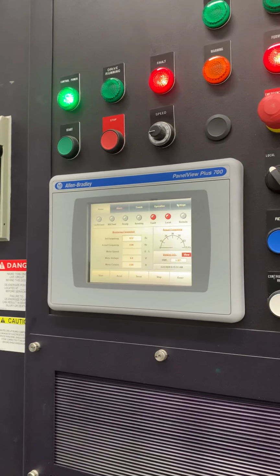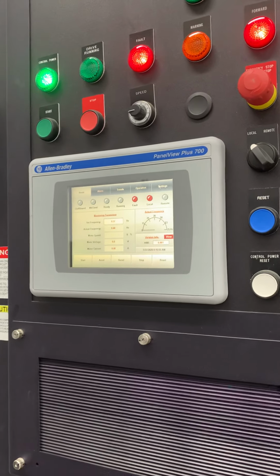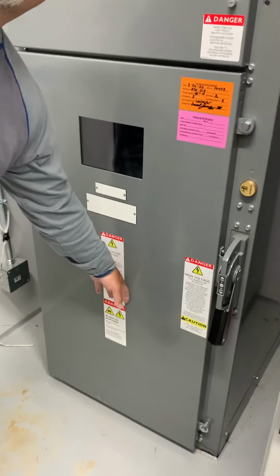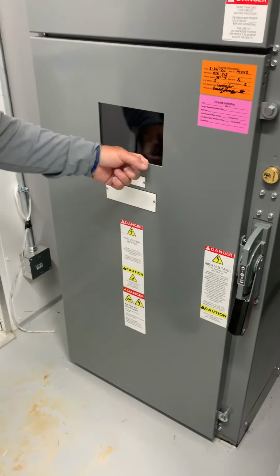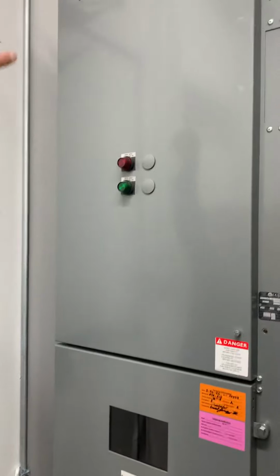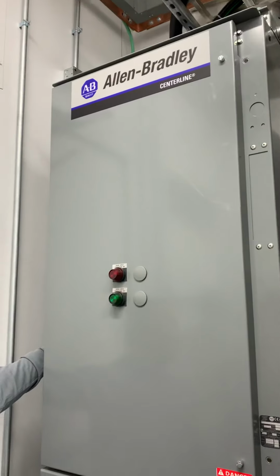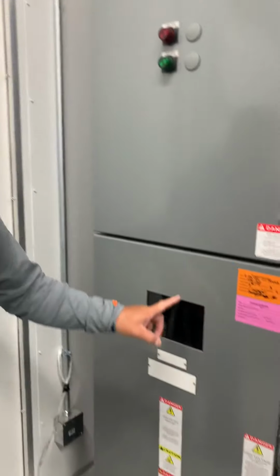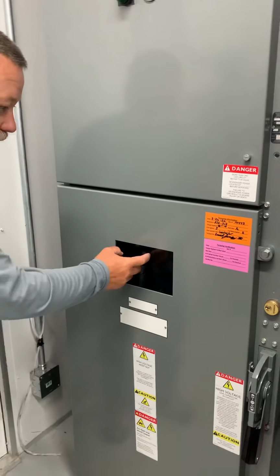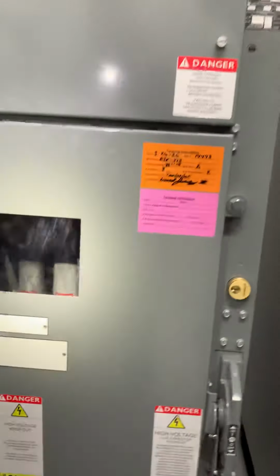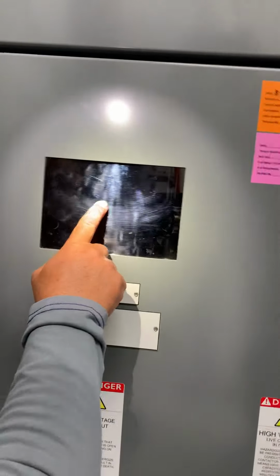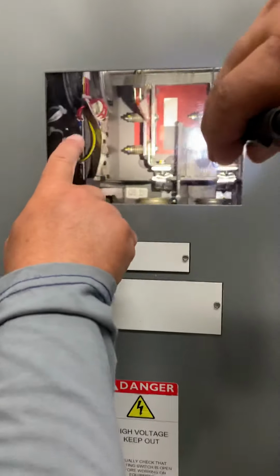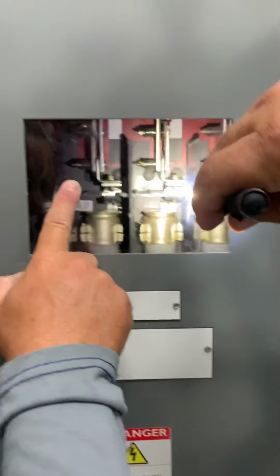So really, that's about all there is to it. Inside here, if you unbolt this and look down there, you've got your vacuum contactor at the bottom, and your fuses. Your main power comes into the bus in the back and comes down. The blades, if you look in this window in the very back, you'll see those white shutters. That's back here in the top.